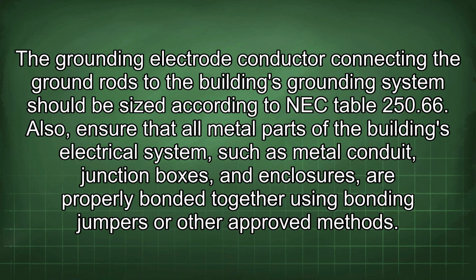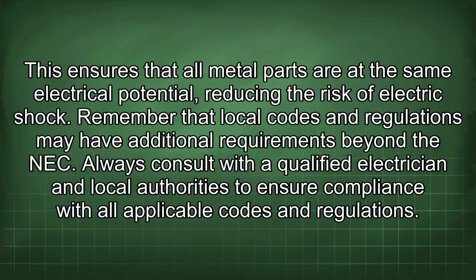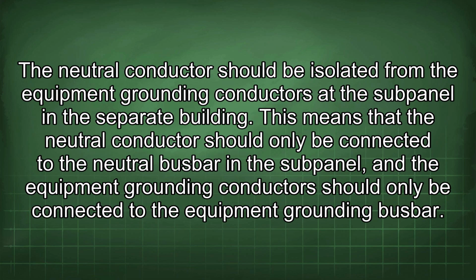Also, ensure that all metal parts of the building's electrical system, such as metal conduit, junction boxes, and enclosures, are properly bonded together using bonding jumpers or other approved methods. This ensures that all metal parts are at the same electrical potential, reducing the risk of electric shock. Remember that local codes and regulations may have additional requirements beyond the NEC. Always consult with a qualified electrician and local authorities to ensure compliance with all applicable codes and regulations. The neutral conductor should be isolated from the equipment grounding conductors at the subpanel in the separate building. This means that the neutral conductor should only be connected to the neutral busbar in the subpanel, and the equipment grounding conductors should only be connected to the equipment grounding busbar.